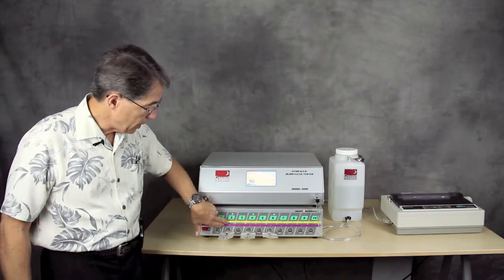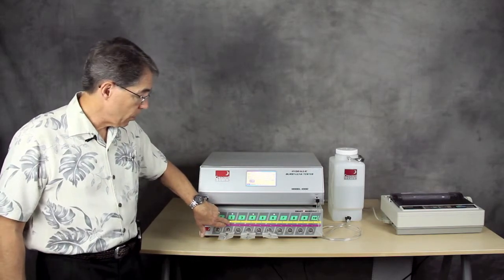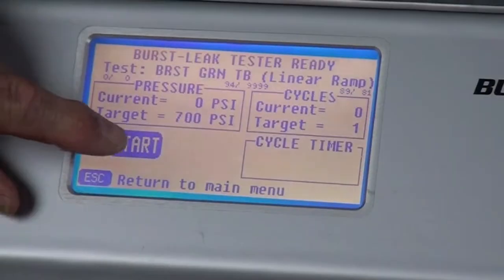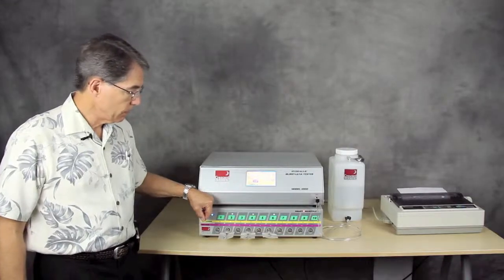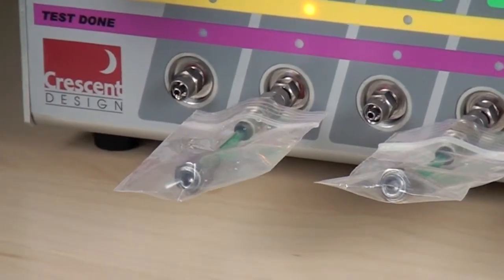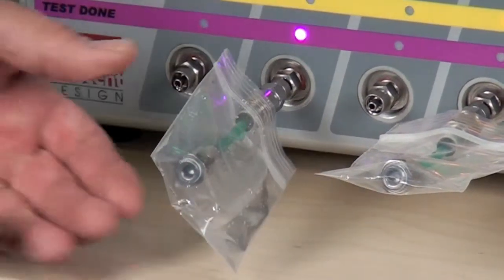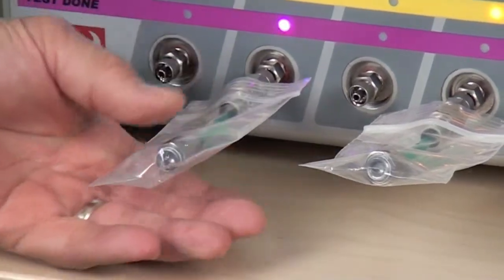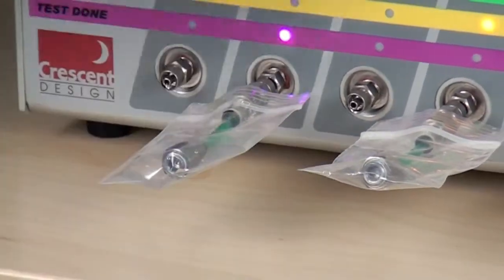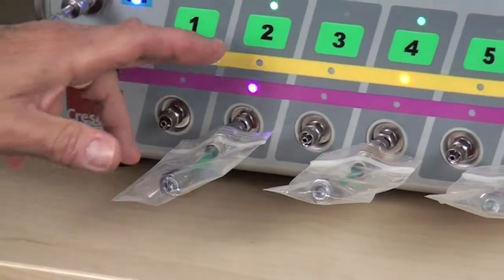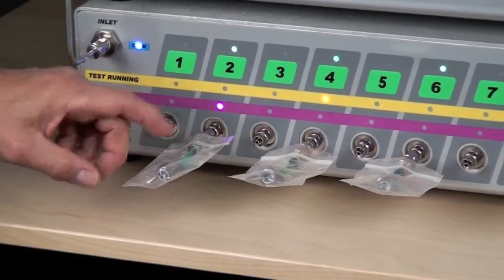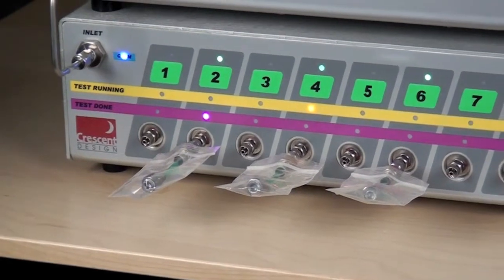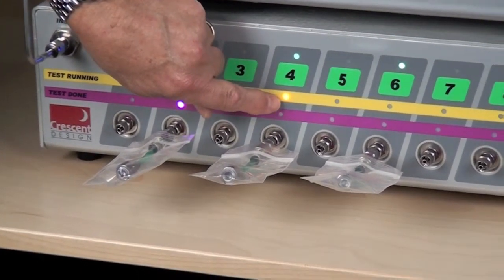You'll notice that the HBLT has selected port 2 first. And we're going to hit start. So what happened there was it selected port 2 and it ran it to pressure and it burst. The machine is now preparing itself again for the second port.